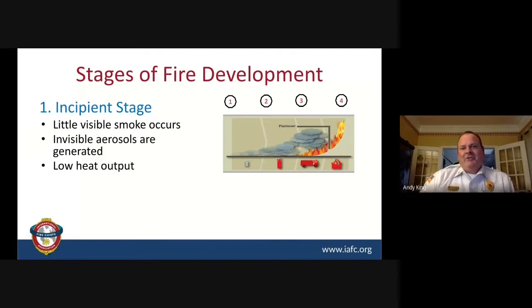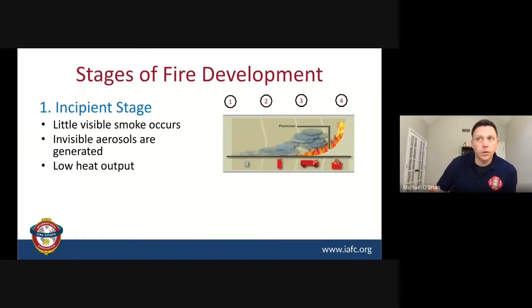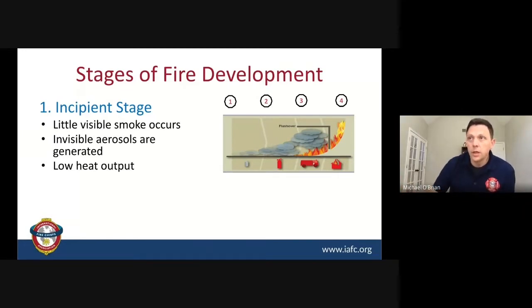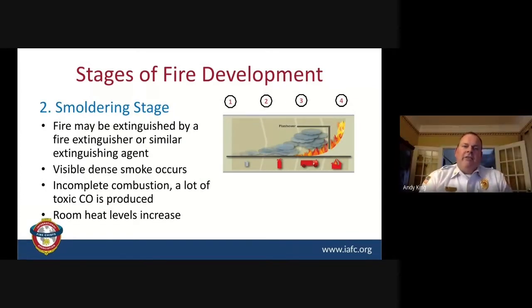Sometimes we go to house fires where we have a little bit of smoke, but yet the smoke alarm in my house may not activate because it's not really considered dangerous. On a commercial system with a smoke detector, they may be more sensitive. So I think the point is we're still getting the automatic alarm coming in during that first stage, the incipient stage of fire. Many times in the incipient stage, it could be the activation of our fire alarm system from somebody seeing a small fire, recognizing and manually activating the system through a manual pull station. But really that incipient stage for us is that reminder — little smoke, low heat output. A little different as we transition to that next stage, that smoldering stage, where you have a lot more smoke obscuration, which should definitely set off most smoke detectors at that point.